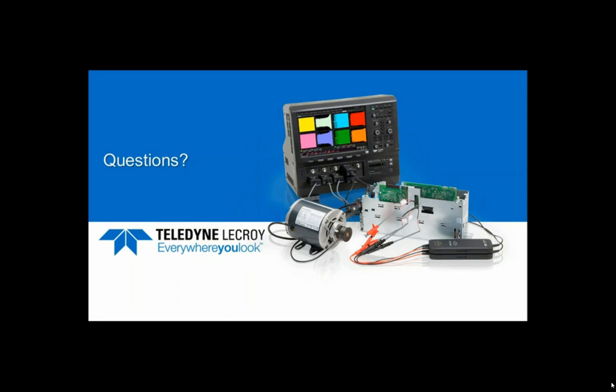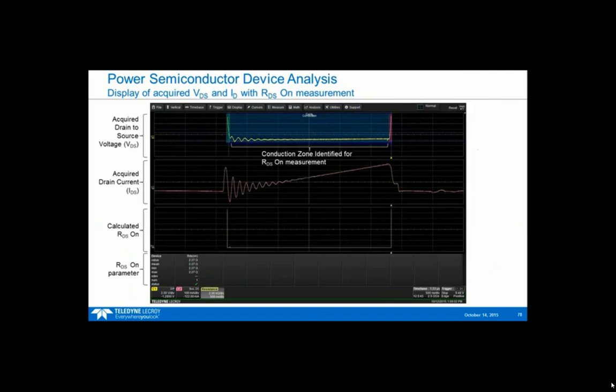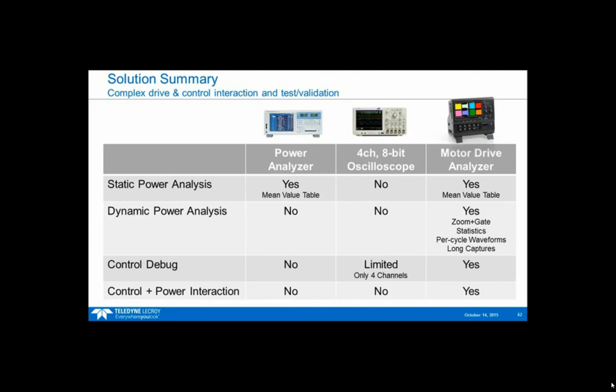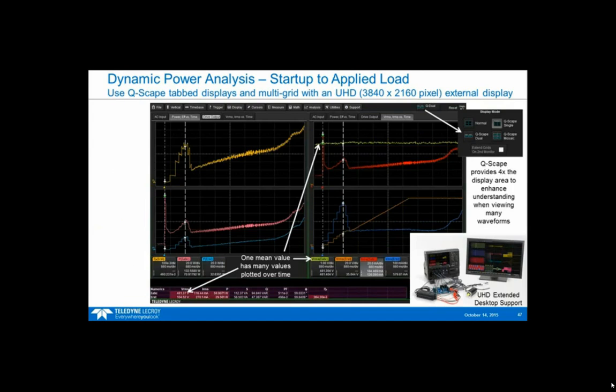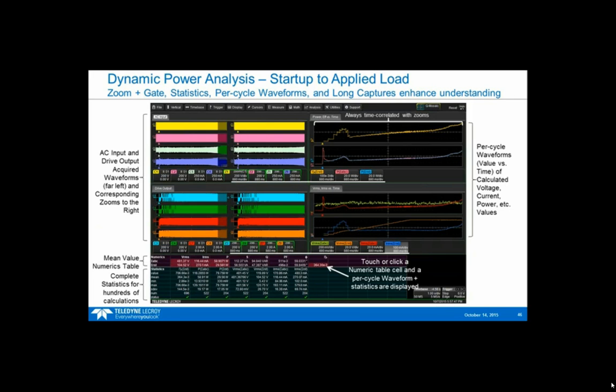Good question. Going back to one of the earlier examples, the AC induction motor is a pretty good example. Here you can see I have the AC input and the drive output, and I'm calculating power factor right there. The displacement power factor usually refers to the distorted waveform of the PWM output — that would be this value right here — and then the real power factor would be the power factor on the AC input.